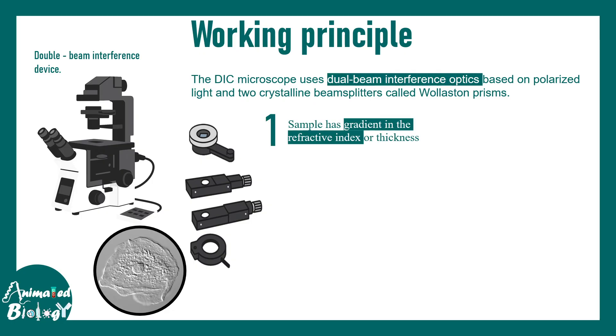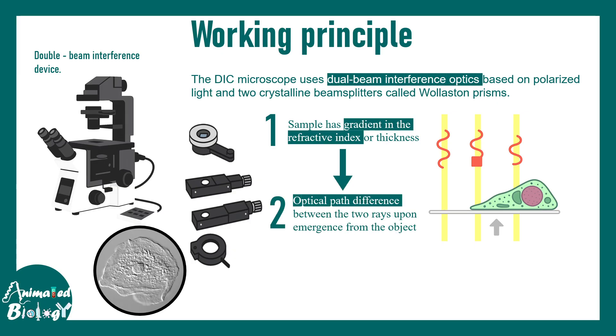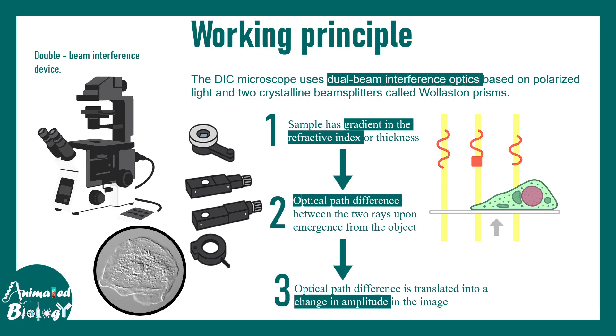The overall working principle is very simple. The sample should have a gradient of refractive index and different thickness. These differences in thickness and refractive index would eventually be translated into differences in terms of brightness and contrast. Light passing through the cell in different locations would encounter different organelles with different refractive indexes, leading to retardation of certain waves. The principle which forms the contrast is the optical path difference, which is translated into a change in amplitude in the image.